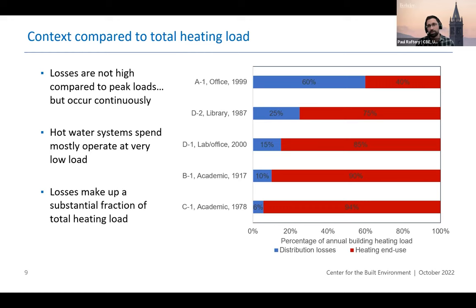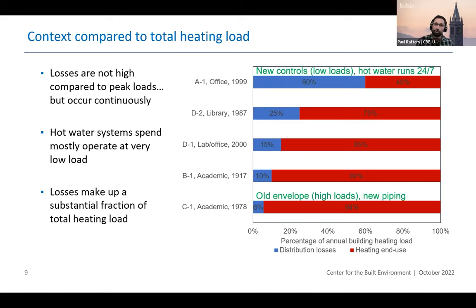For five of these buildings we have annual data from the instrumentation, and the losses range from somewhere between 6% in one building to 60% in another. That variation is due to some buildings having very high heating loads — like a really old envelope, single pane windows — whereas others have newer construction, better insulation, and also some of the controls and strategies in place.